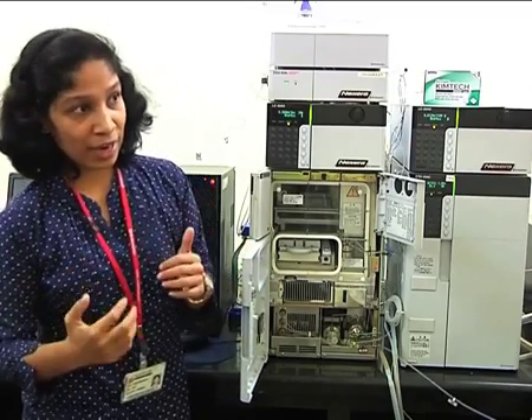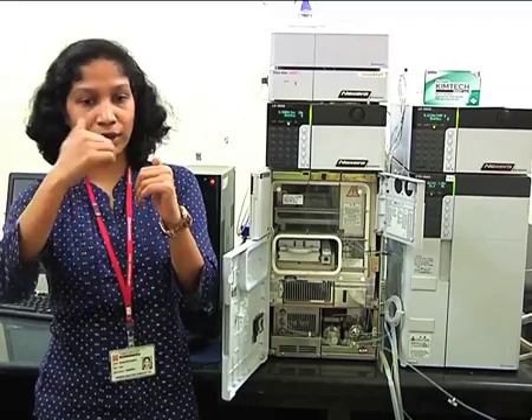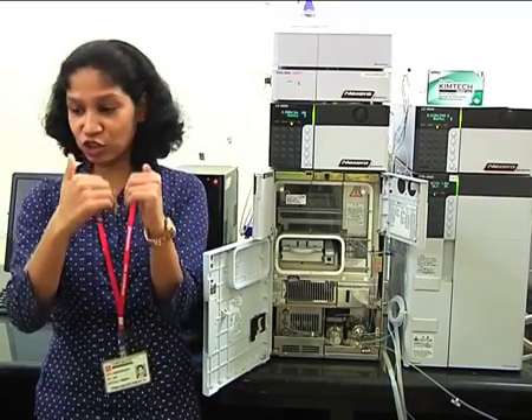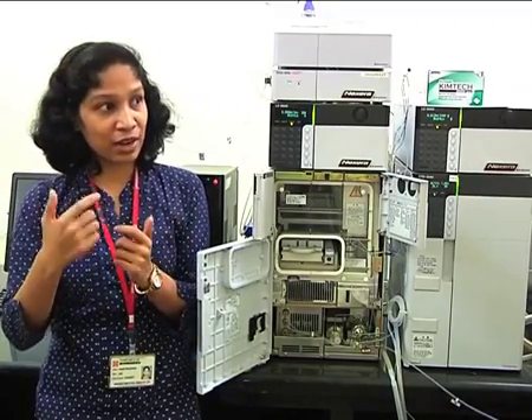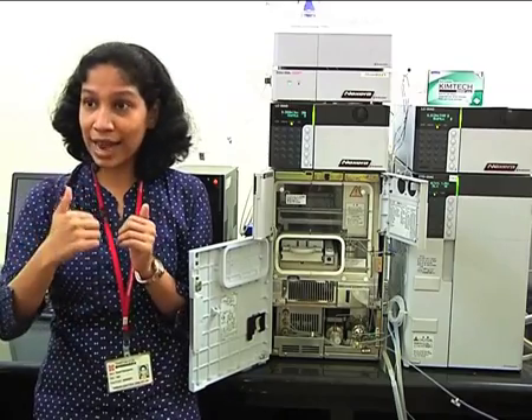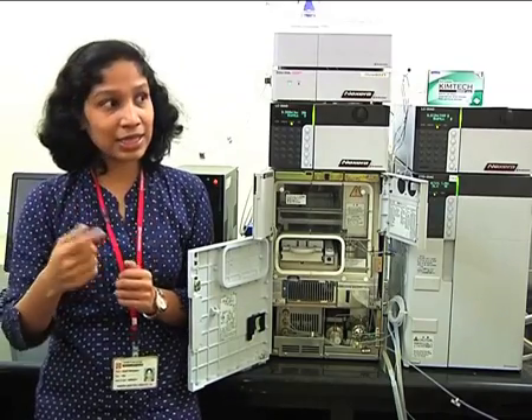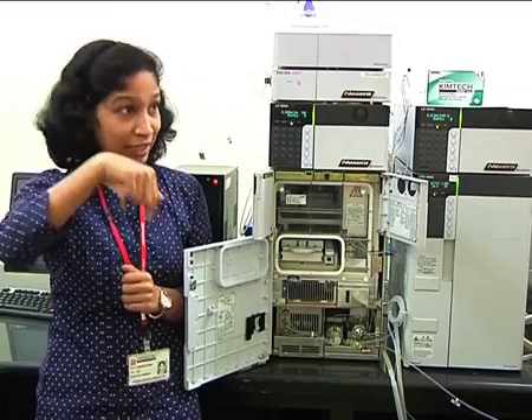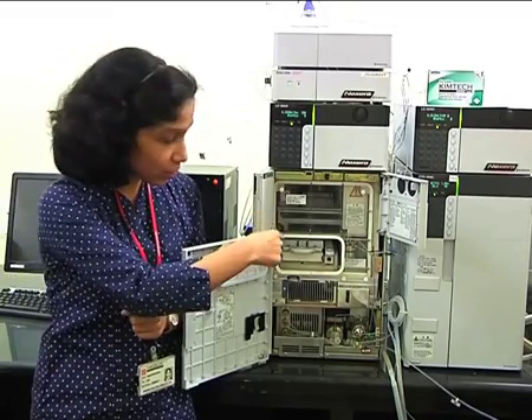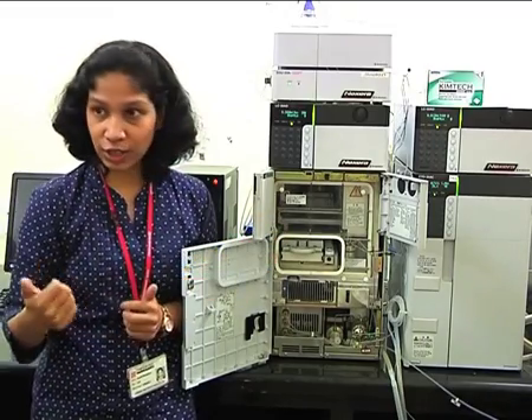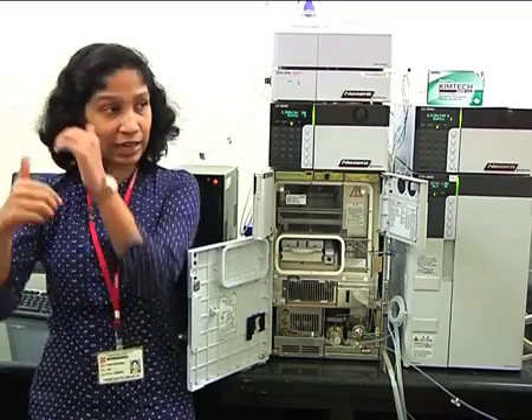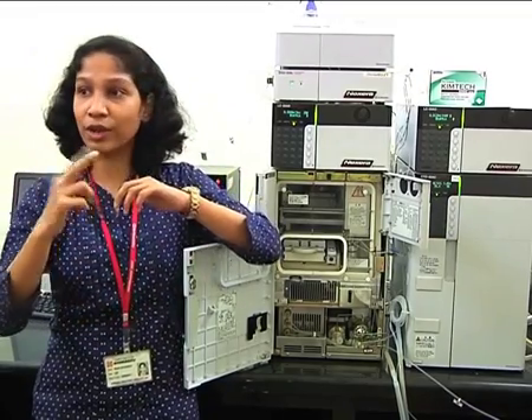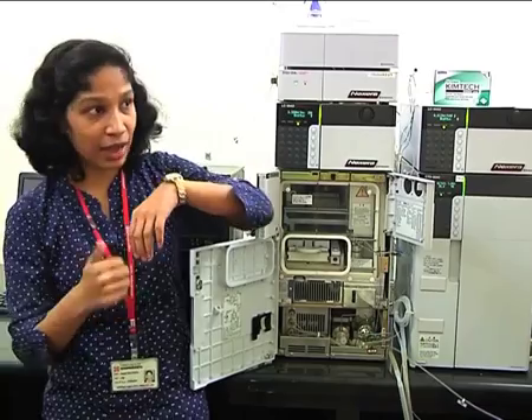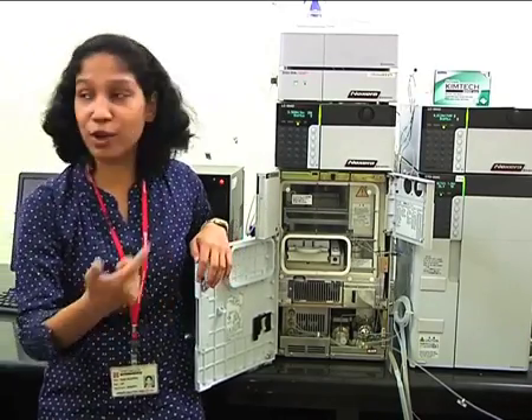Thirdly, carryover can come when there is contact between your needle and the injector port. But if I reduce this contact area, there is less chance of sample getting deposited on the injector port. So in this particular autosampler, the design of the injector port and needle is such that there is minimum contact area between the two, and that also does not allow carryover to take place.